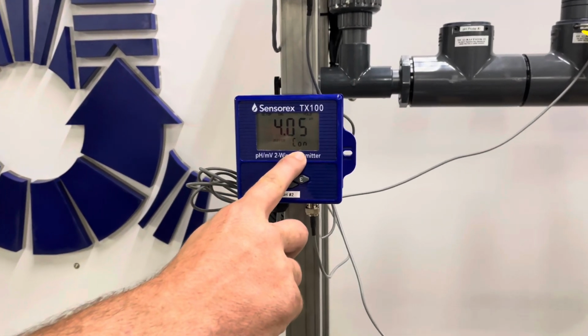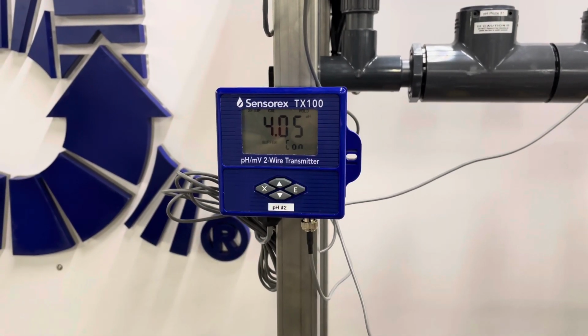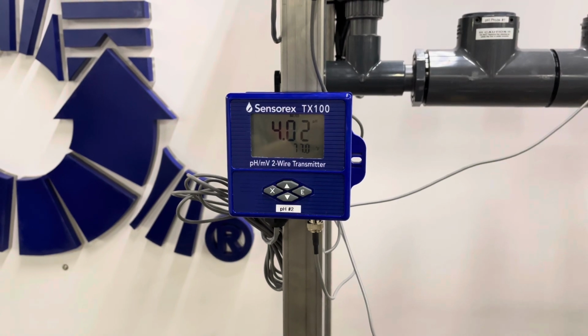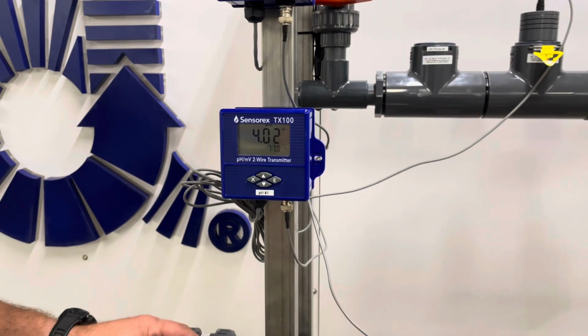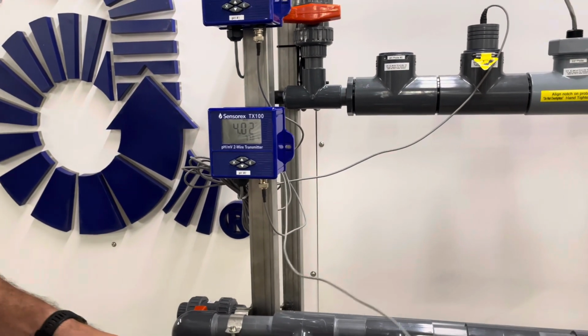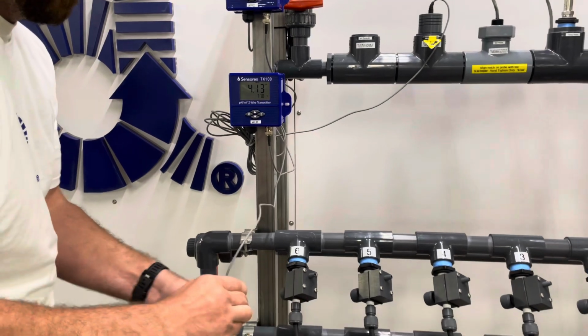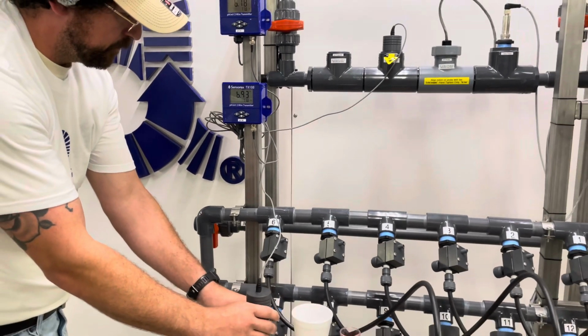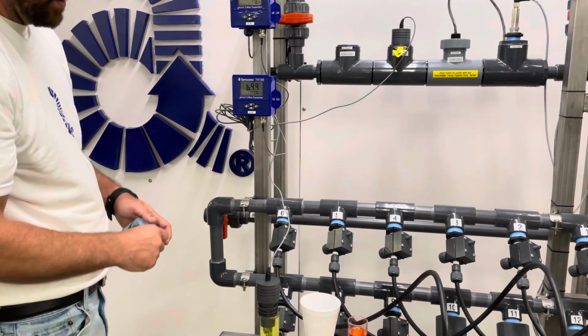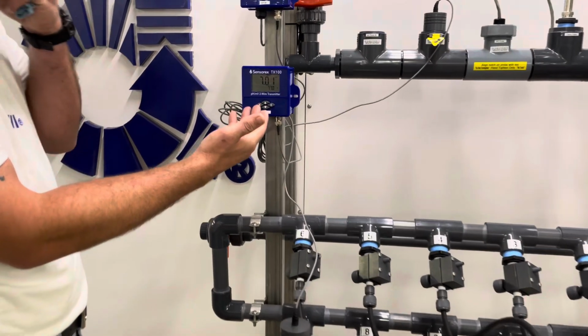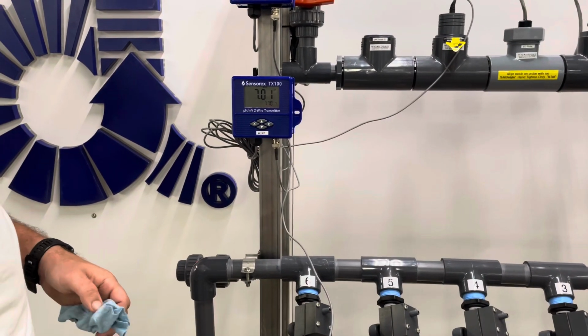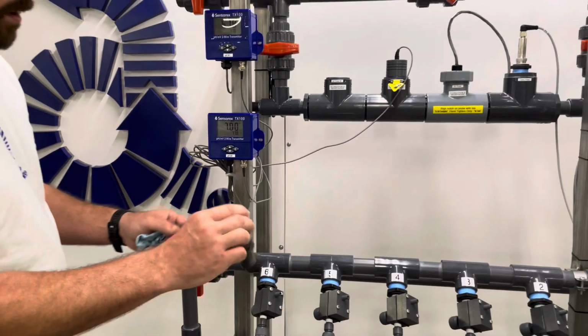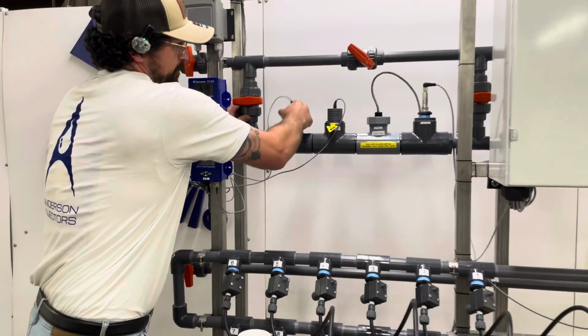It's telling you CON for confirm. Give it about 10 seconds and you'll see your reading. And we'll put it in the 7 solution to verify. So we put it in 7, we're reading 7. Now that this pH probe is calibrated, we'll put it back in the line.